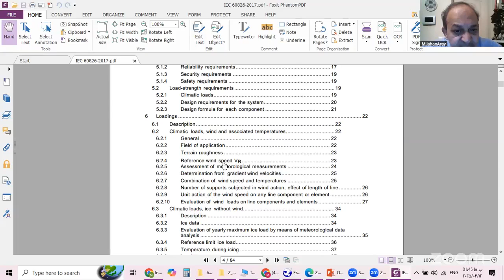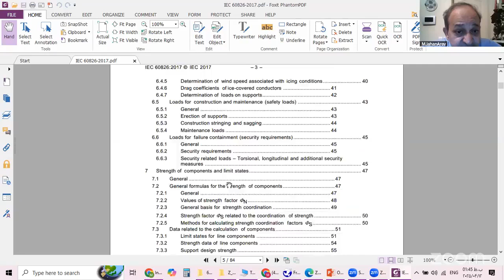The climate loads: combined wind and ice, or ice without wind. They offer formulas for this and also safety factors, and when you go into the details you can calculate all these loads yourself. As I explained in the lecture, there are loads for construction and maintenance — that means safety loads — and loads for failure containment. Section 7 defines criteria and strengths of all components: cables, towers and structures, foundation.